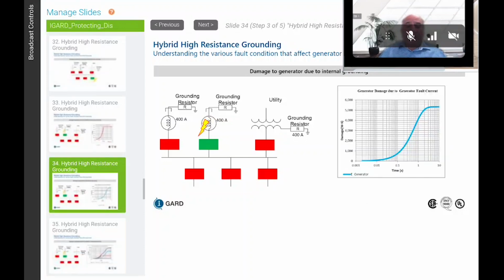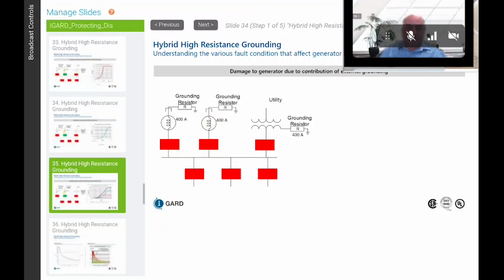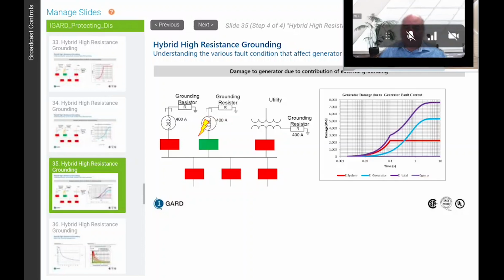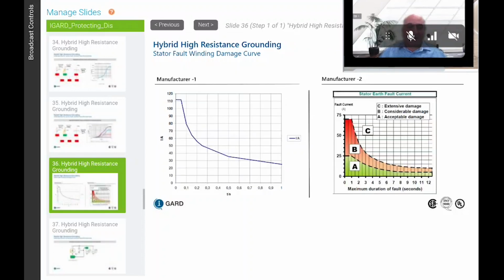Now, what we haven't done is clear the source from the resistor. And this is the amount of damage that occurs to the generator after the breaker is opened. So as protection engineers, the only thing we can do is open the breaker, but we haven't protected the fault from the source. So if we do everything together, we end up with this. In 100 milliseconds, we've cleared that fault for differential and 5-cycle breakers. Internal fault, the cyan, and the purple one is the total heat caused.